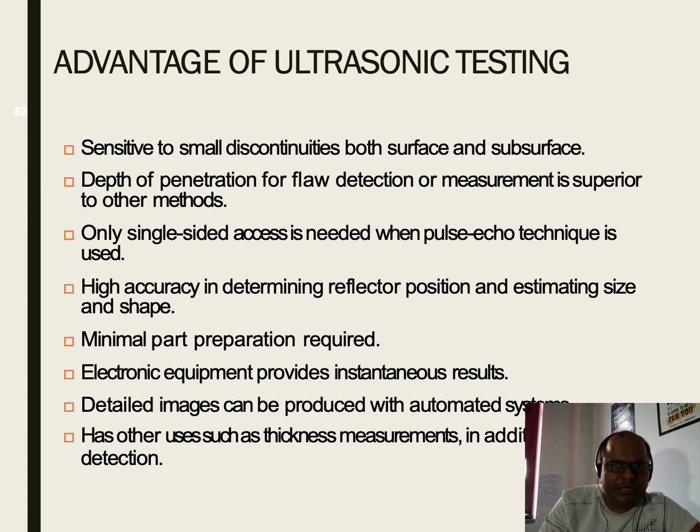What are the advantages of ultrasonic testing? Sensitivity to small discontinuities, both surface and subsurface. Depth of penetration for flaw detection and measurement is superior to other methods. Only single-sided access is needed when the pulse echo technique is used.